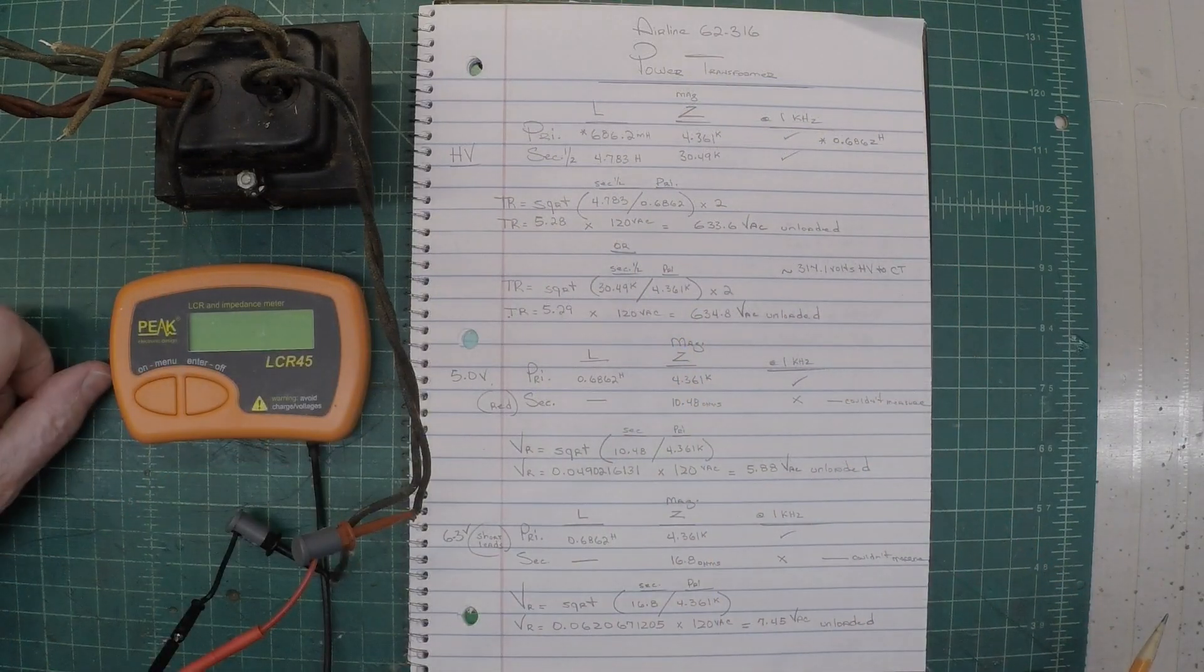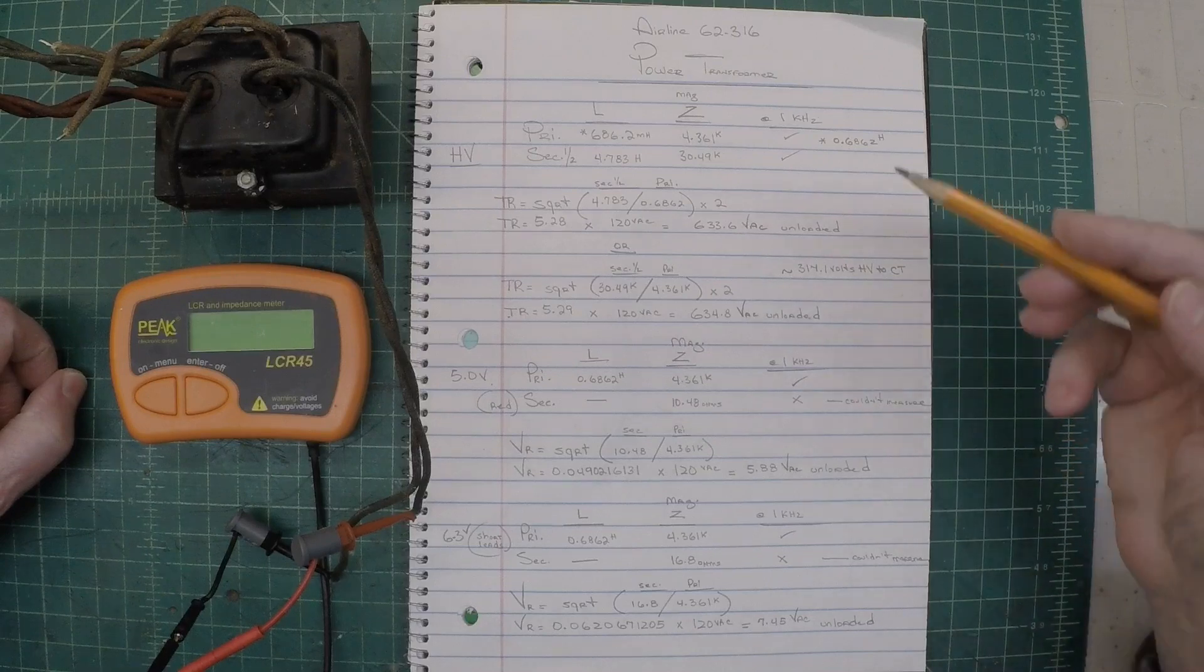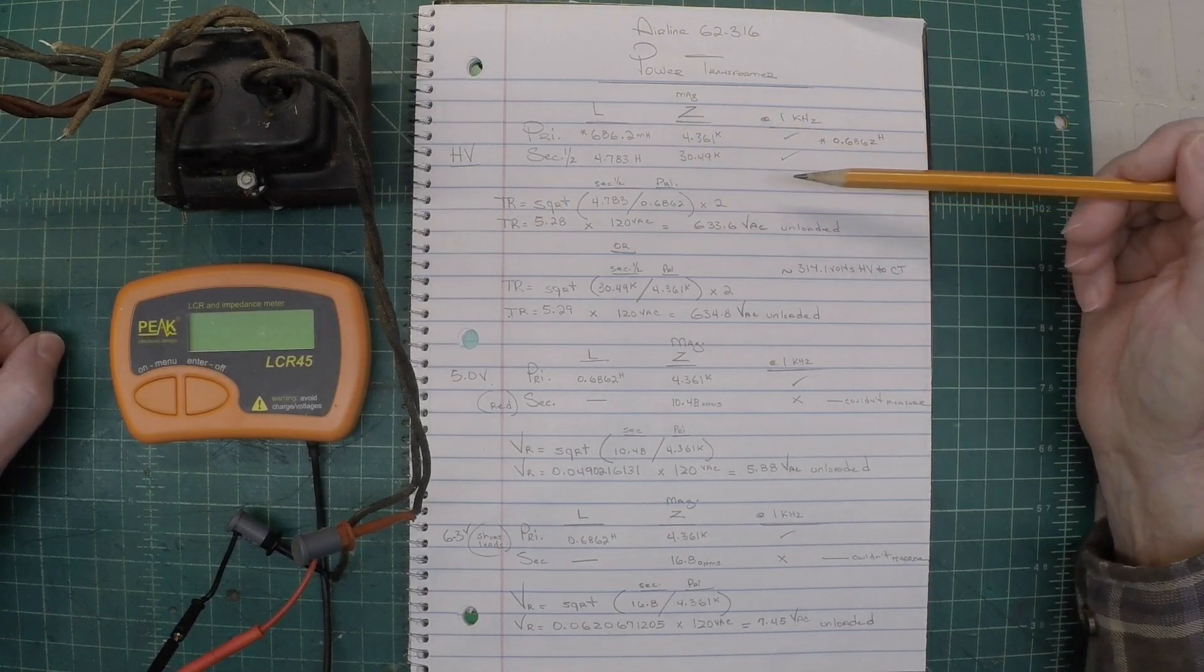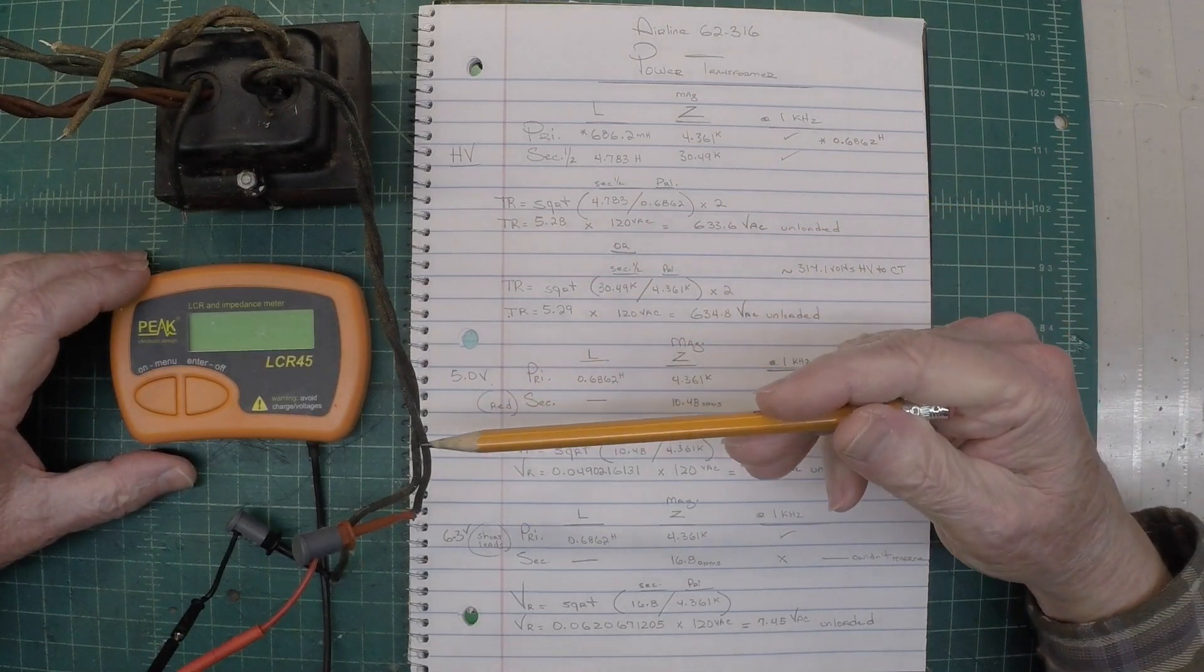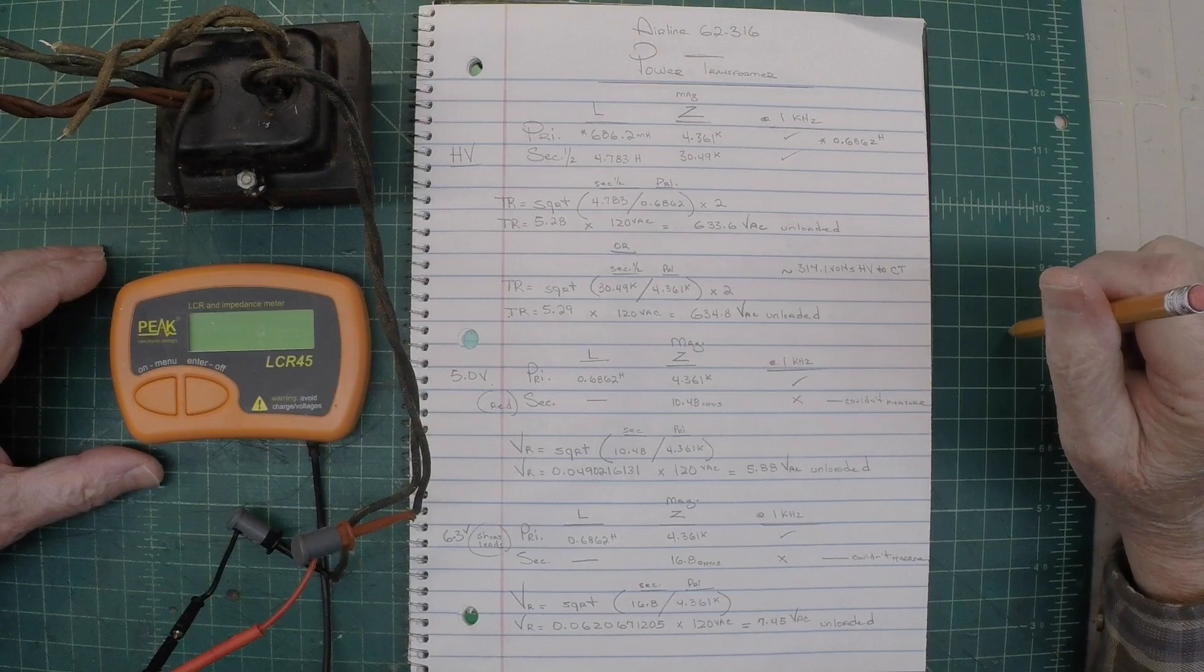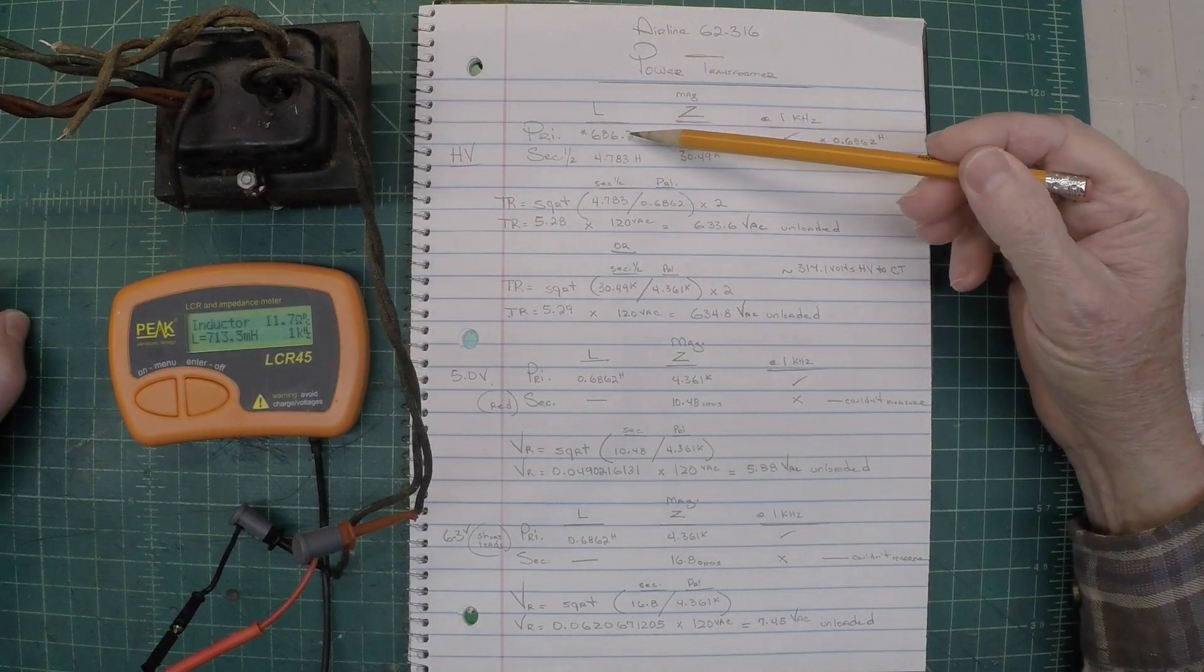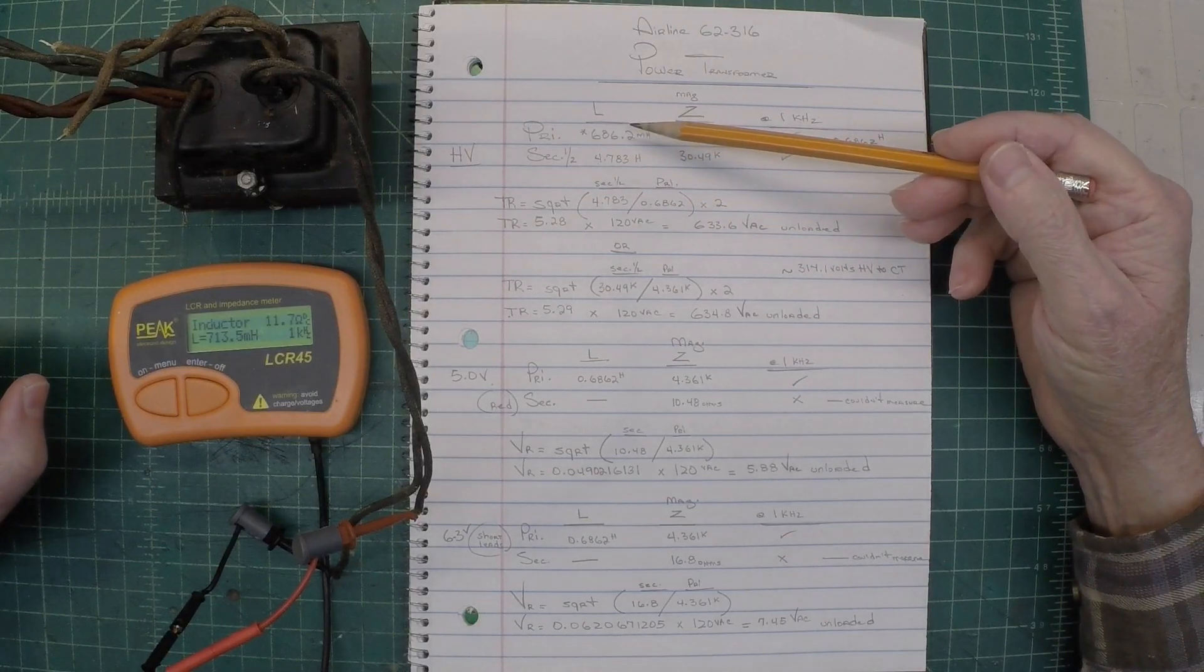As I mentioned, you can actually calculate the turns ratio or voltage ratio by using the impedance from the meter itself and or the inductance. So I've already done the math here, and I'll demonstrate that. I'm just hooking the LCR meter up here to the primary side. I took these readings early this morning. It was about 20 degrees cooler here in the shop, and sometimes that will impact the measured results. So we'll stick with these numbers since I've already recorded those.